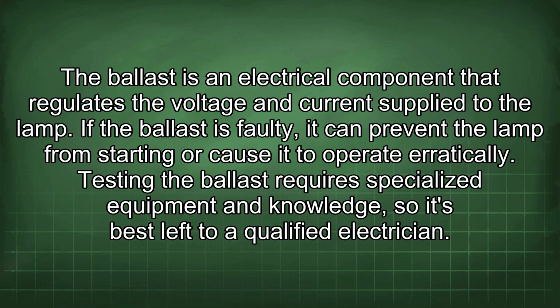The ballast is an electrical component that regulates the voltage and current supplied to the lamp. If the ballast is faulty, it can prevent the lamp from starting or cause it to operate erratically. Testing the ballast requires specialized equipment and knowledge, so it's best left to a qualified electrician.